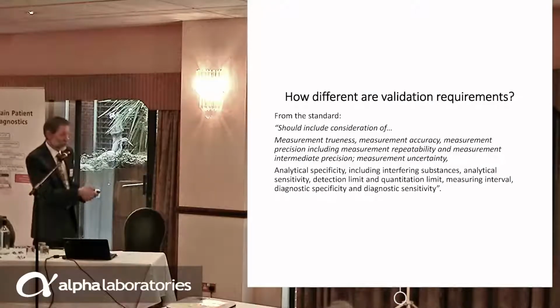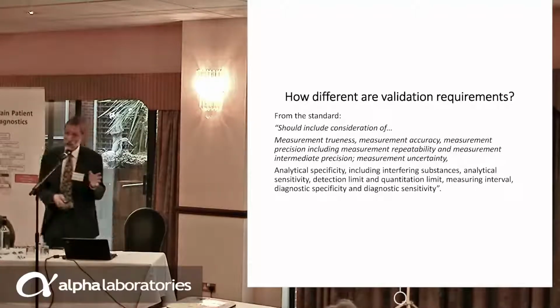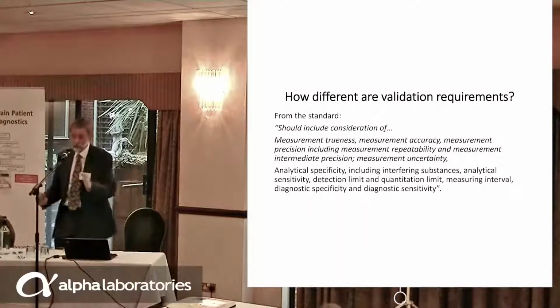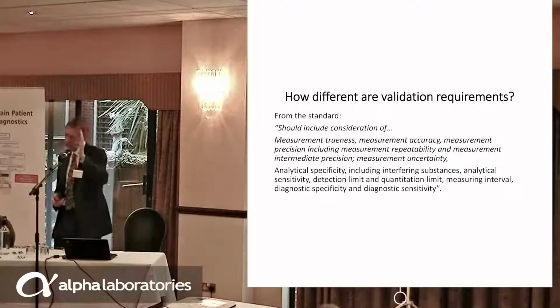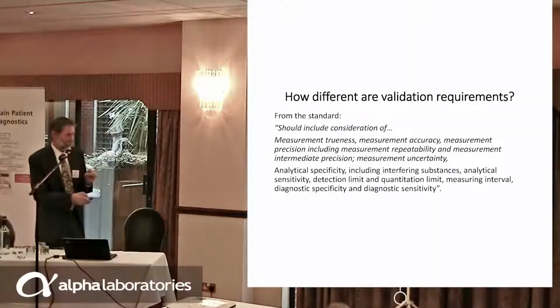But you may also want to do the things that hopefully, if it was a validated method by a manufacturer, they would include. So specificity: are there interfering substances? For instance, if you've got a cortisol assay that you're running by mass spec, you set it up and you think, okay, that mass transition is going to be associated with cortisol, because that's what it says in the literature, and we look for it and it's there and it seems to correlate. But what if you've got other similarly structured glucocorticoids or mineralocorticoids in your sample that could potentially have similar transitions? You may want to explore those.